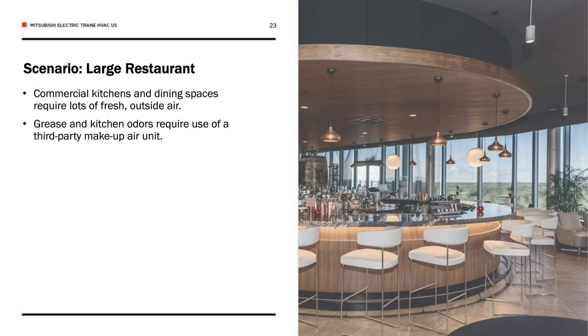Let's look at a scenario like a large restaurant. VRF systems provide energy-efficient comfort, and fluctuating heating and cooling loads as a guest transitions from one space to another can be uncomfortable. However, even if the restaurant uses a DOAS to provide conditioned outdoor air to staff and guests, the amount of grease and debris produced by the commercial kitchen systems means that a restaurant typically requires third-party packaged rooftops and makeup air units.